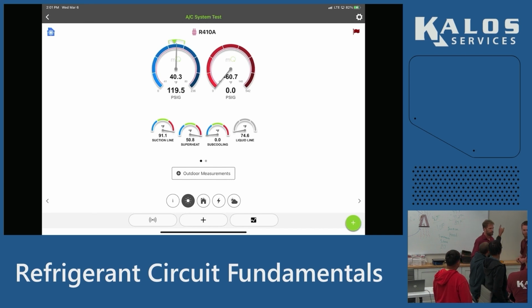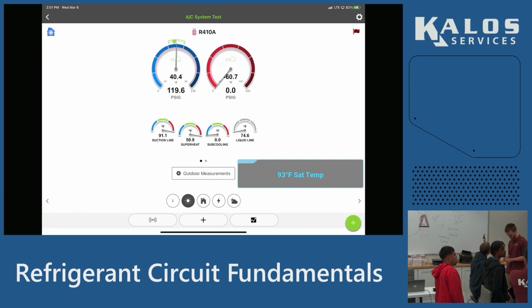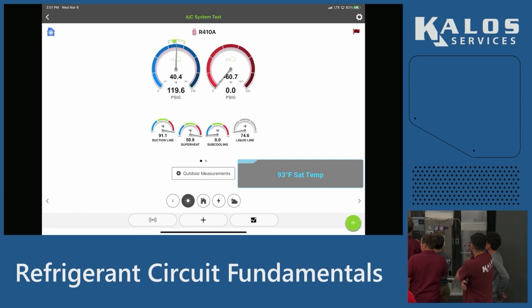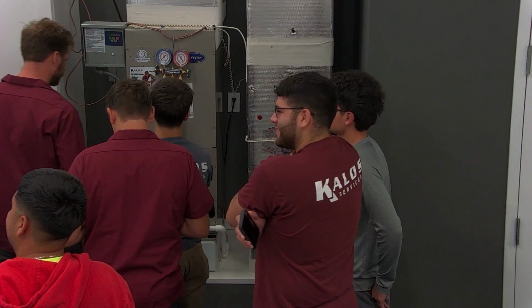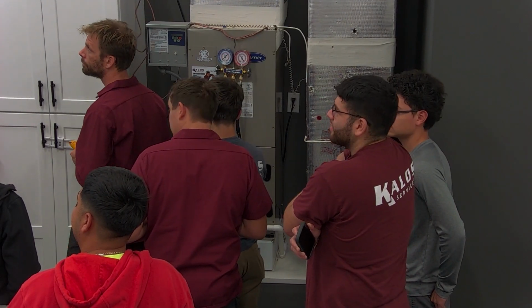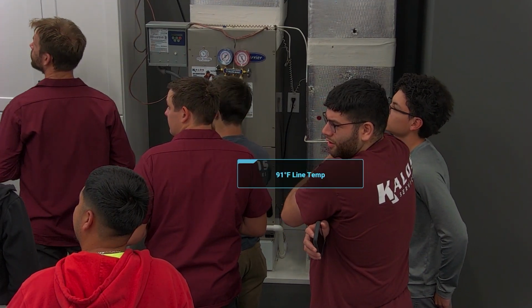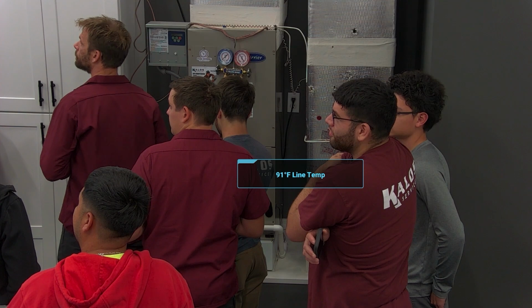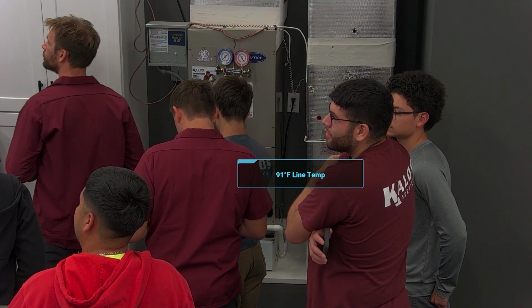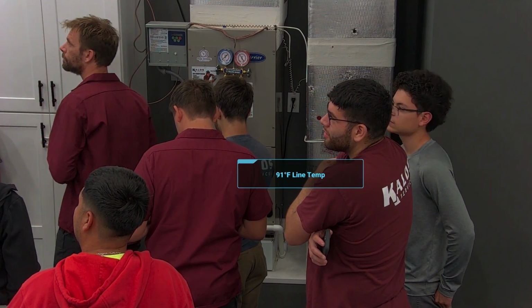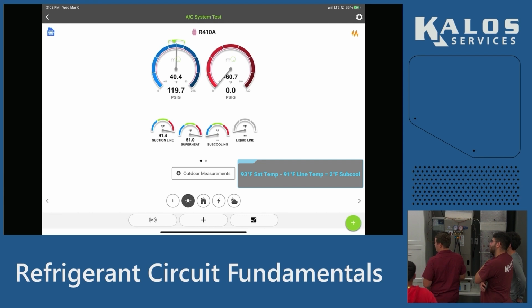What's the saturation on it? Oh, 91. It's actually 93. What number are you using for your line temperature? The liquid. Well, can we check saturation? Oh, it's a suction line. Yeah. There you go. 2 degree subcool. Yes.